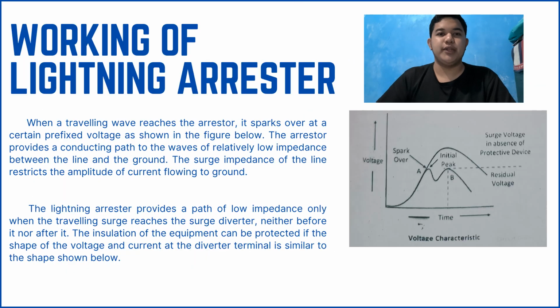Here's the working principle of a lightning arrestor. So how does a lightning arrestor work? When a traveling wave or surge reaches the arrestor, it sparks over once the voltage exceeds a preset level. This creates a low impedance path for the high voltage surge, allowing it to flow harmlessly to the ground. Because the surge impedance of the line limits the current, only the surge energy is discharged, protecting the system from damage.